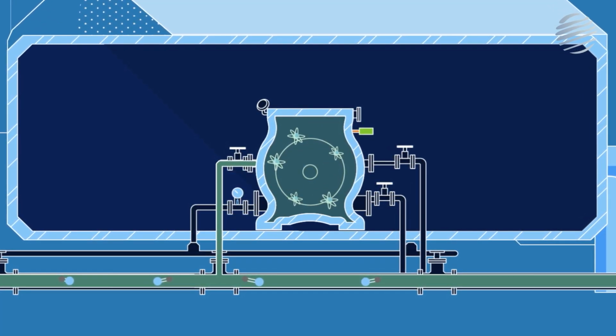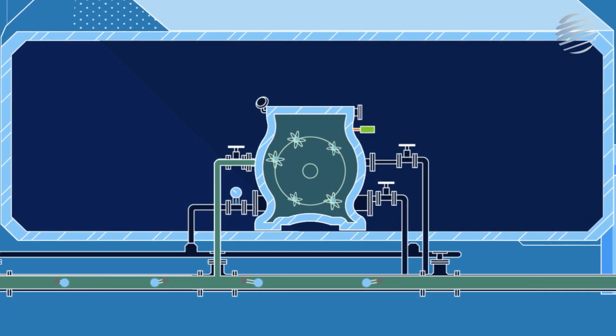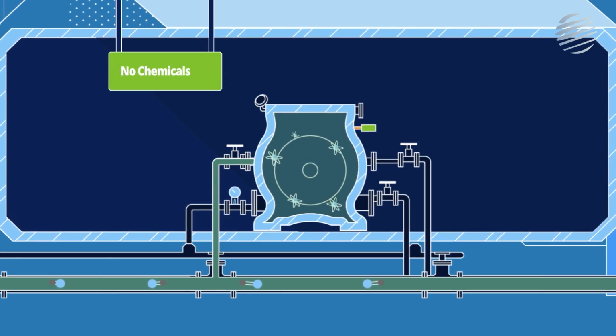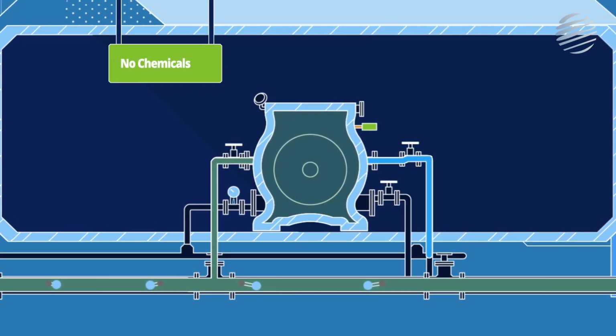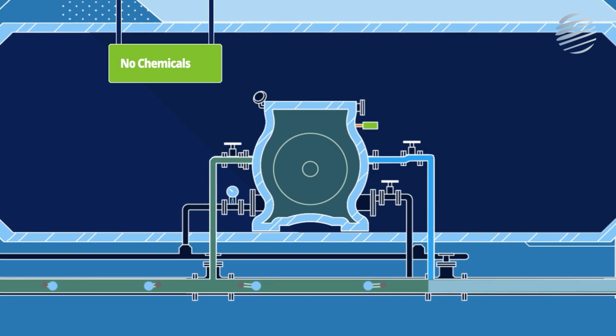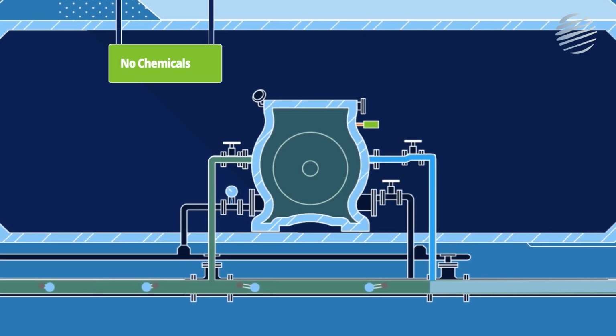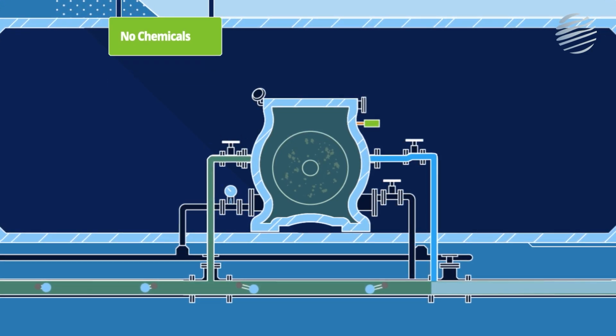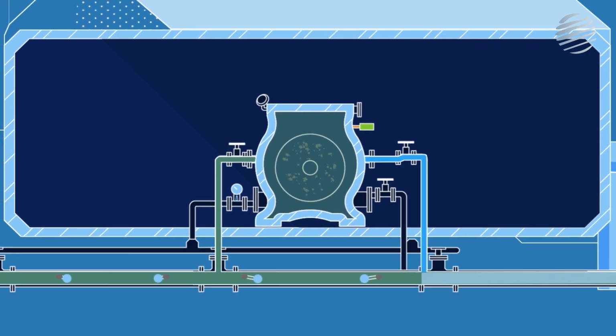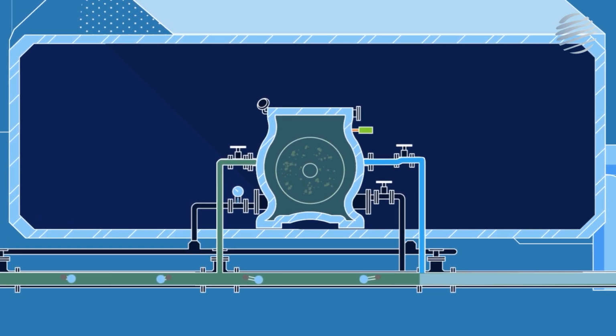This process generates chlorine and additional strong oxidants on demand, disinfecting the water and eliminating bacteria and other biological contaminants, such as Legionella bacteria. The unique environment creates scale inside the reactor, instead of in your water cooling system.